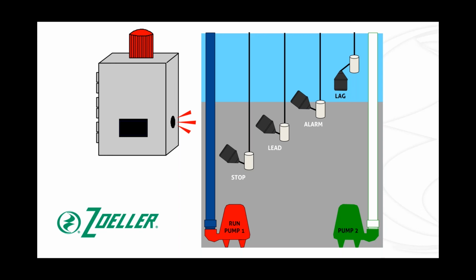It could simply be because there was a higher than normal water flow rate coming into this pit. Maybe this is on a house. Maybe somebody has a big giant jacuzzi tub up in their master bedroom and they've just drained it and it's pouring in here faster than the pumps could keep up. But again, the thing that I want to point out to you is that I have opted to put my alarm before my lag float. And the reason I have done that, if you think about this, if I had put my lag float before my alarm, what would have happened? Well, pump 2 would have been called to operate. It would have come on, maybe it would have taken care of the situation.